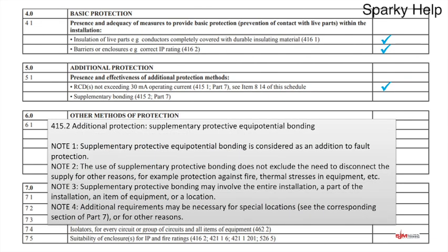a tick. And what does that basically say there? Additional protection, supplementary protective equipotential bonding, and we've got some notes, and it says note 1, supplementary protective equipotential bonding is considered an addition to fault protection. So it's an enhancement, which is what additional protection is. Note 3, supplementary protective bonding may involve the entire installation or a part of an installation or an item of equipment. And it also says additional requirements may be necessary for special locations, hence it does say part 7.